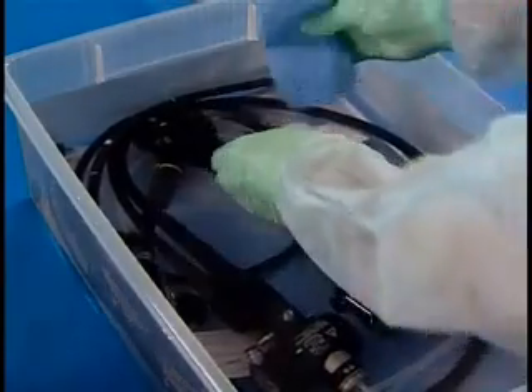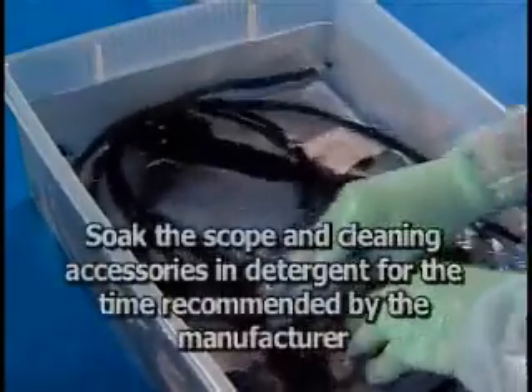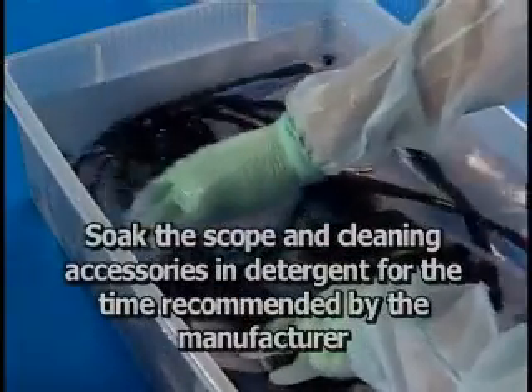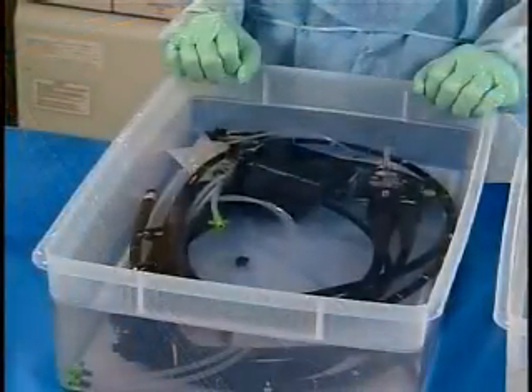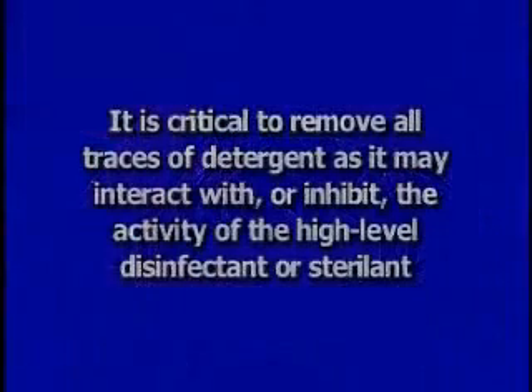Now that the internal channels are filled with detergent, wipe the external surfaces with a soft sponge or lint-free cloth to remove any debris. Soak the endoscope and accessories in detergent for the time recommended by the detergent manufacturer. The next step is to rinse the detergent from the endoscope. It is critical to remove all traces of detergent, as it may interact with or inhibit the activity of the high-level disinfectant or sterilant. Transfer the endoscope and accessories to a basin or sink filled with clean water.